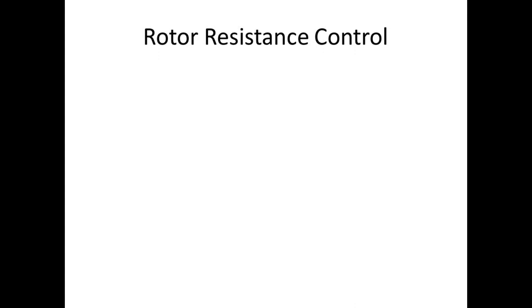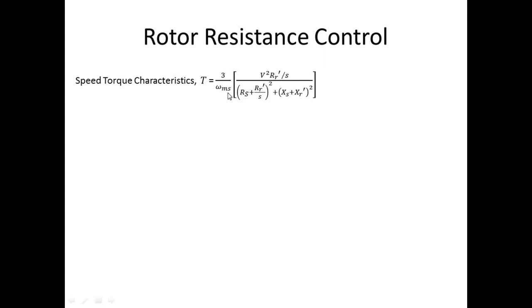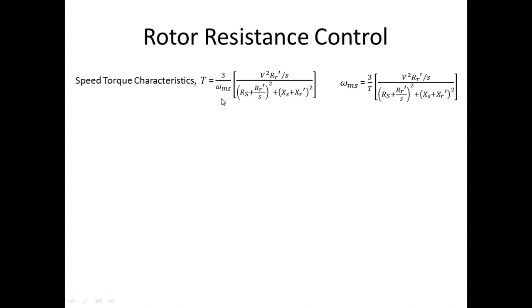In an induction motor, the torque is equal to 3 by omega_ms times V squared times Rr_dash by s, divided by (Rs + Rr_dash/s) whole square plus (Xs + Xr_dash) whole square. So we can control the speed or the torque-speed characteristic by controlling this rotor resistance Rr_dash. That is the principle of rotor resistance control.